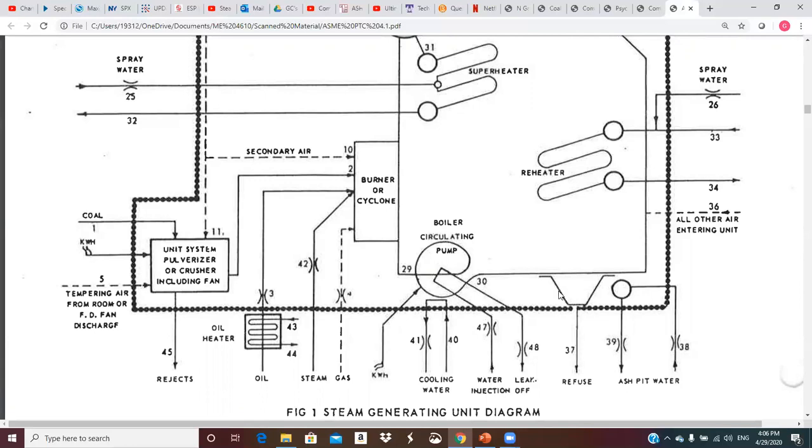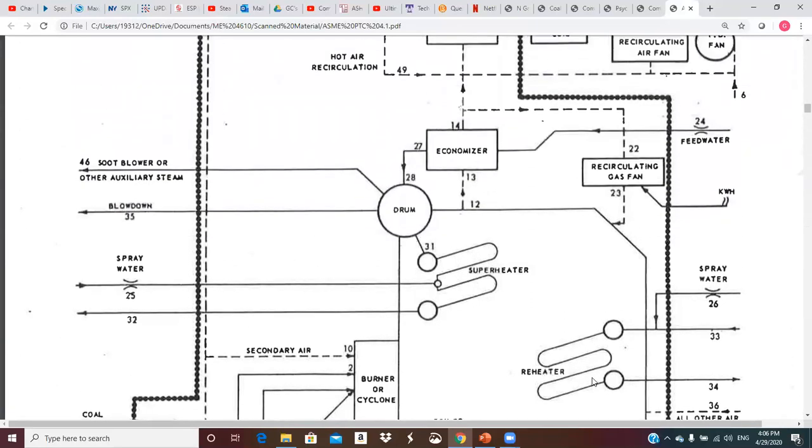We could have water injection and water leak off. So we could have some additional water coming in here. We might have dry refuse, clinkers and things falling down to the bottom of the boiler that are being taken out, mass flow. There's a certain amount of energy that leaves with them. Sometimes we circulate ash pit water down here, have some water down here to make sure we don't start a fire down in the bottom of the boiler.